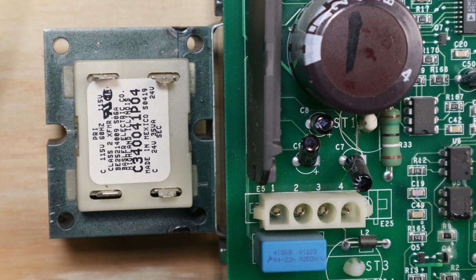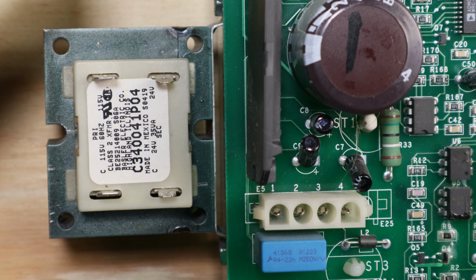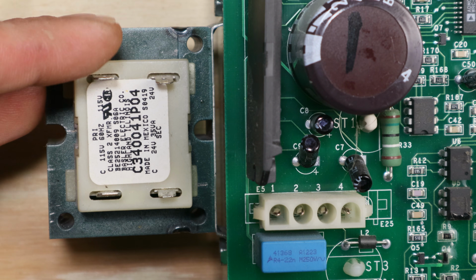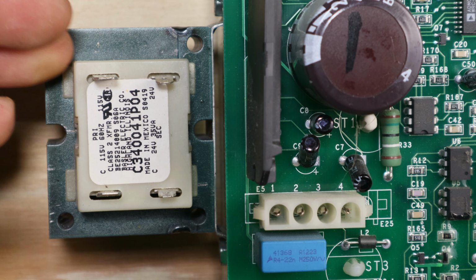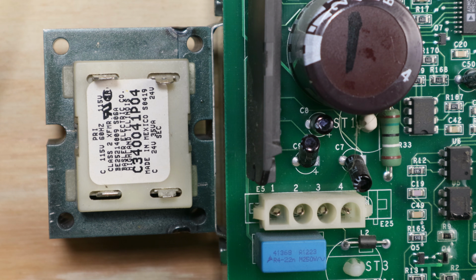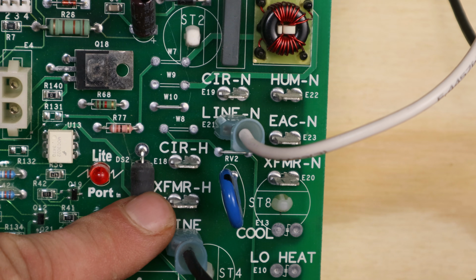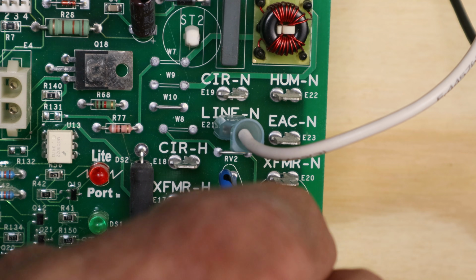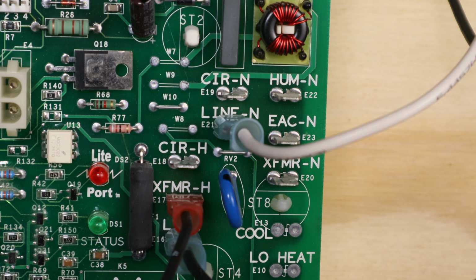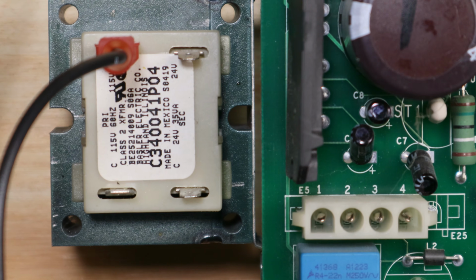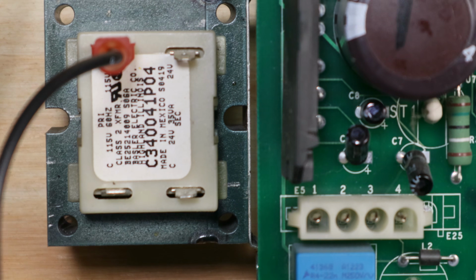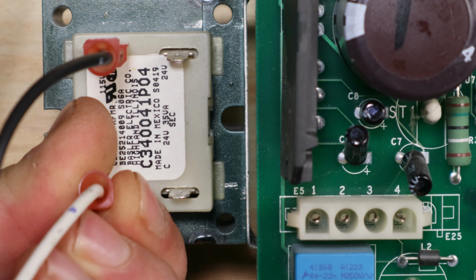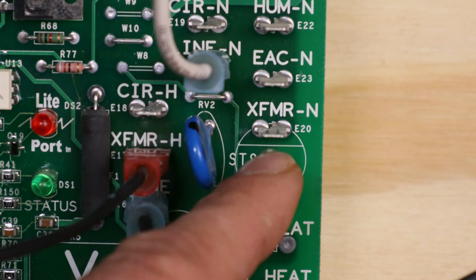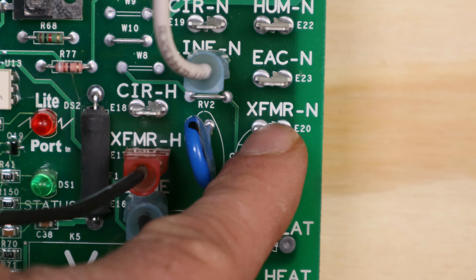Now, one more component we need to get high voltage to is our step-down transformer. So this is going to take the 120 volts we're feeding into our board and step it down to 24 volts that we can use in our control circuit. So that's the voltage for our thermostat, the terminals on our control board that send out the heating and cooling coils and so forth. So to do that, we have a transformer hot. We're going to run that to our primary side on our transformer. So this here's our primary side, and we're going to feed the 120 volts right into there. Now we also have to run the neutral from the primary side back to the control board again. So I'm just going to go ahead and plug the neutral in there. And then back over on the control board, we have our transformer neutral connection right here.